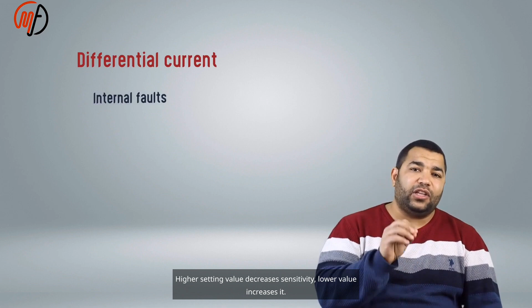Theoretically, but we have set the differential current setting to increase safety and to avoid any false operation or incorrect tripping of the relay due to various practical issues, such as CT errors, for example, which we will explain in detail in the upcoming episodes. Increasing the value of this setting means a decrease in the sensitivity of the relay, while decreasing the value of this setting is equivalent to increasing its sensitivity.